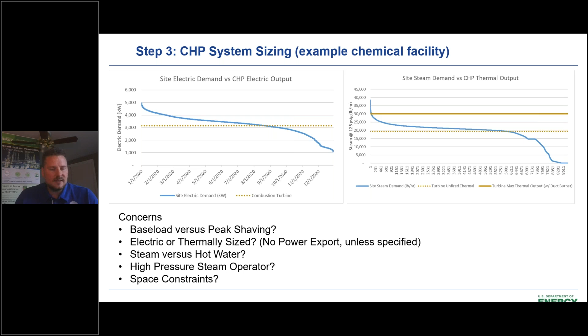So once we're looking at the sizing of the systems, we do at times look at the CHP technology. Sometimes, at some levels, we don't have to worry too much about what CHP technology we're looking at. But if there's high pressure steam at the facility, we're probably going to look at a combustion turbine. But it depends from system to system. And here you can see a graphic of different size systems. If there's a lot of steam at a site, we may look at a steam turbine or a back pressure steam turbine.